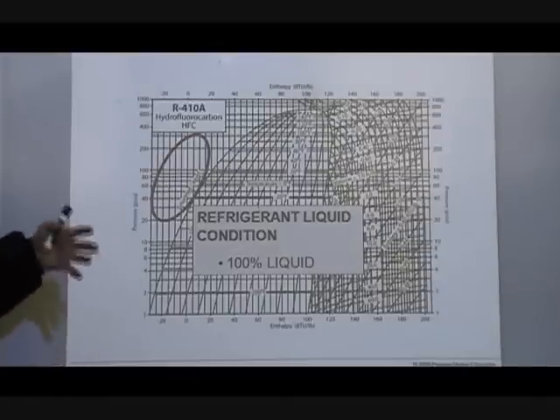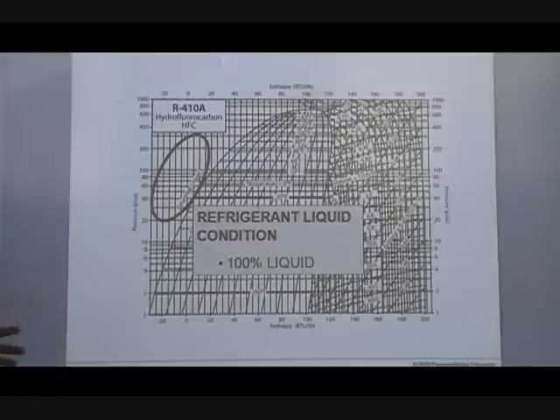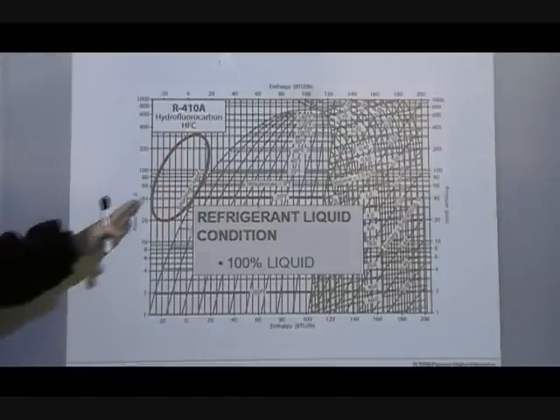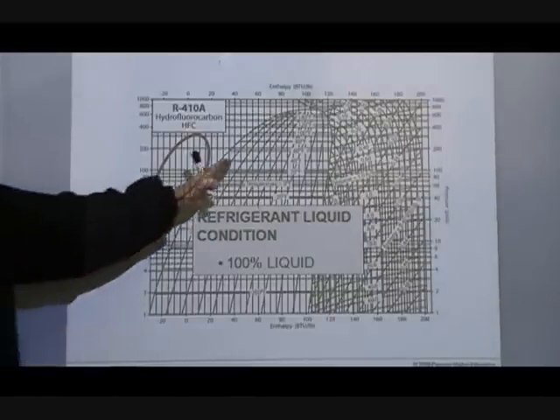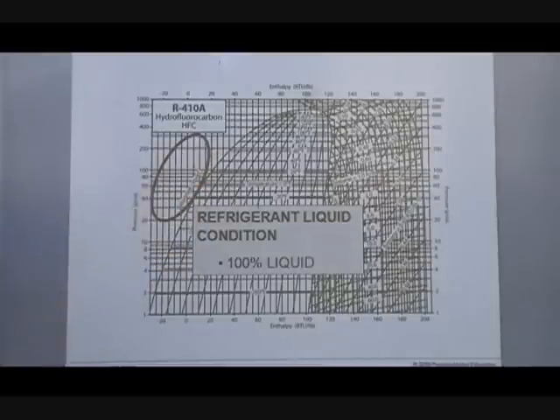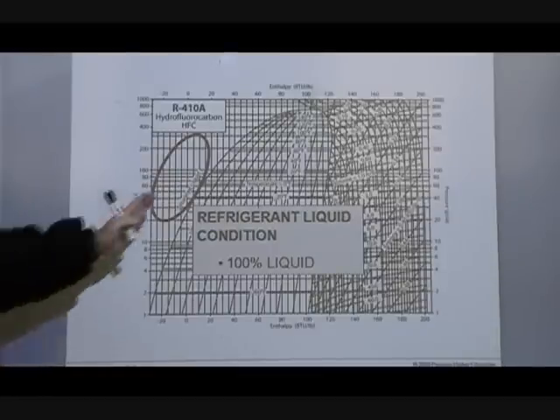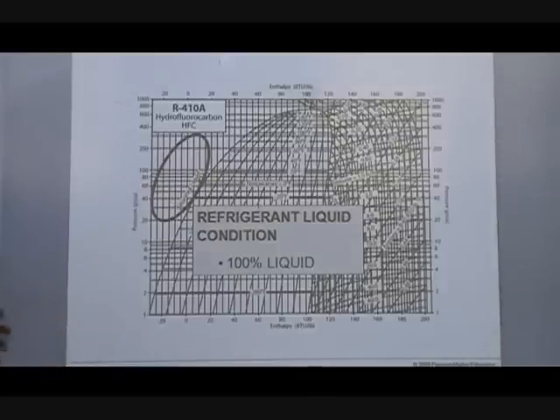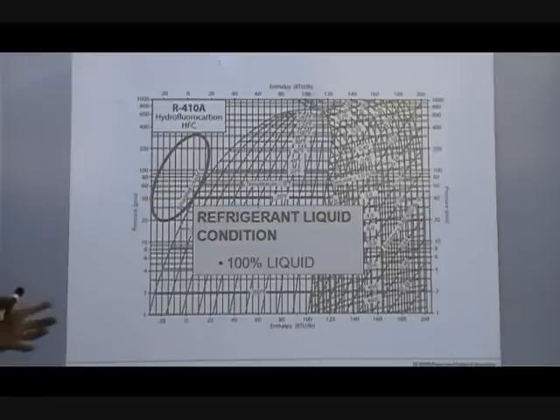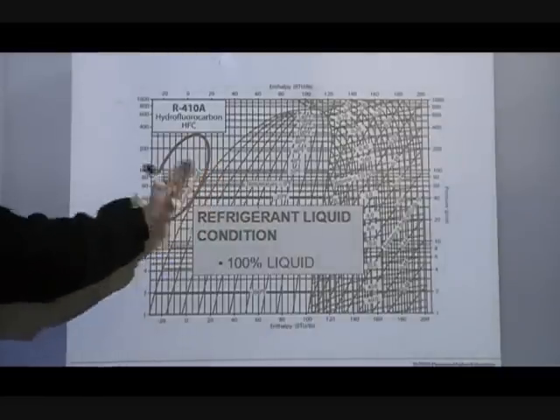Superheat: what is superheat in the refrigeration system, where does it take place, how do you measure it, why is it important? The saturated liquid is the point in the system where you've got 100 percent liquid. All the vapor that's going to condense has condensed and you've got no more heat to be rejected in the form of latent heat. Latent heat is a really powerful force that occurs when the refrigerant is changing states — from vapor to liquid in the condenser side.